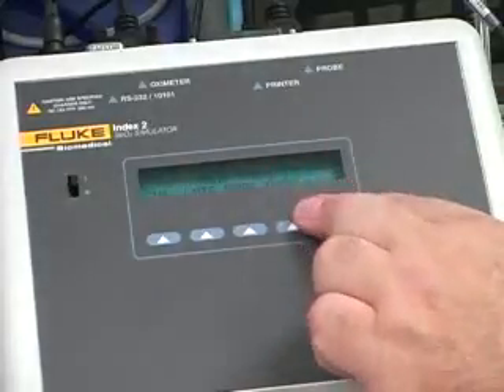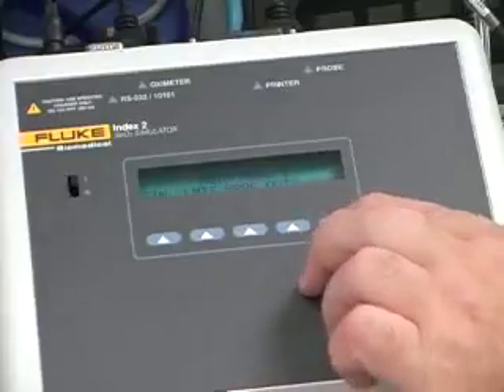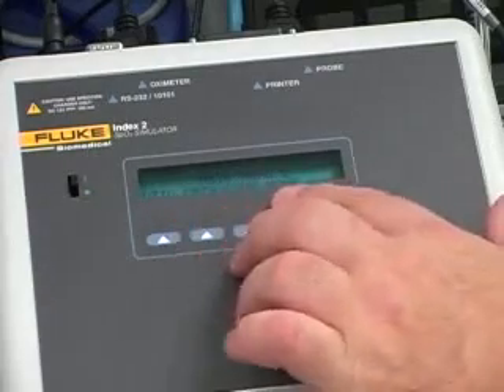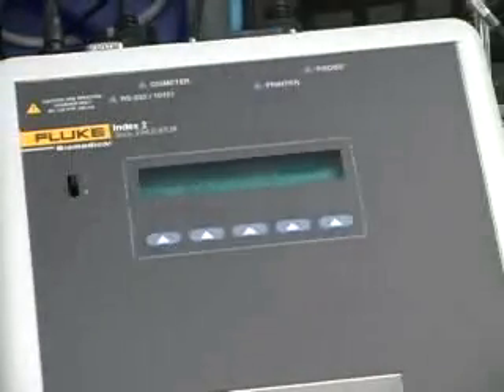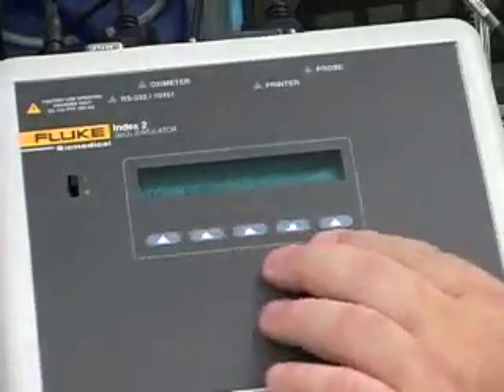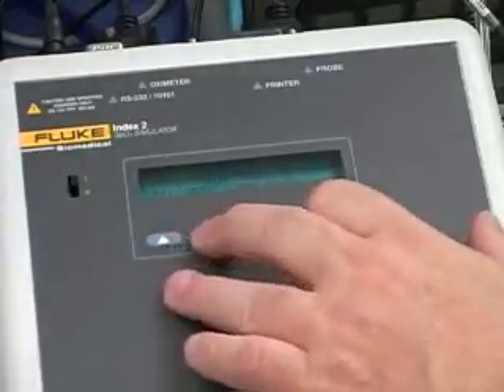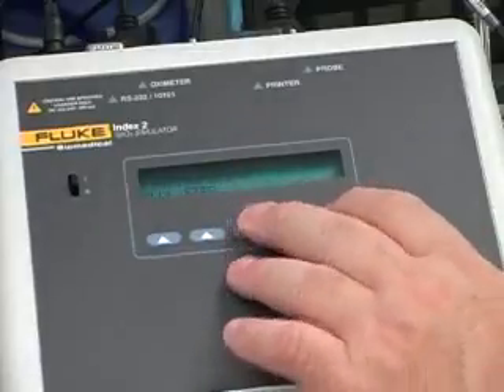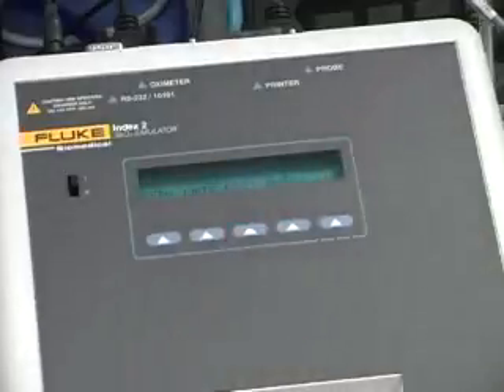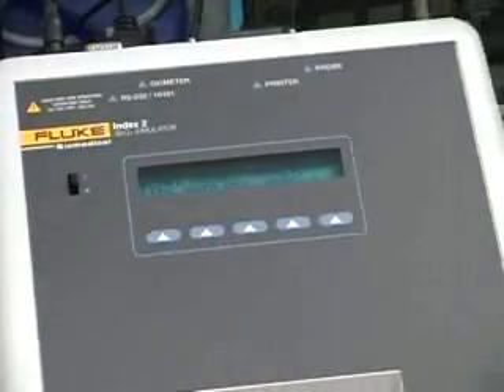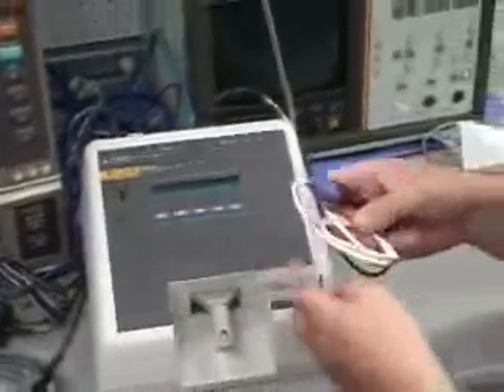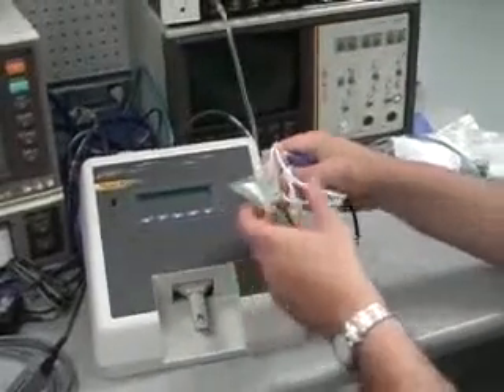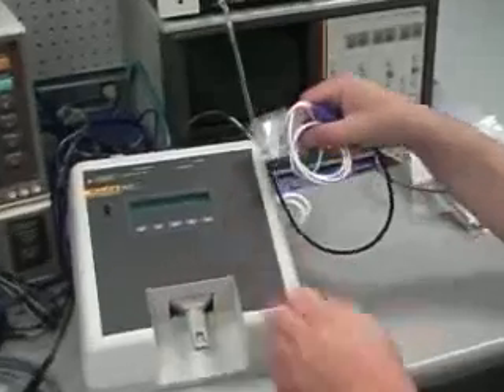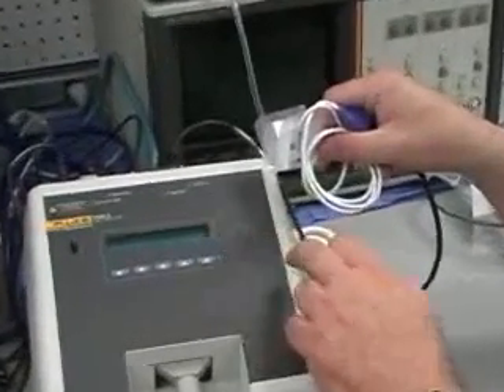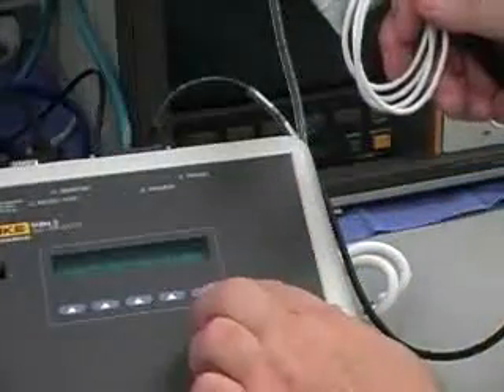Okey-dokey. Auto, we're going to cover more with a med tester. And just a couple of other options. These are more for programming, so I don't want to get into those at this point. And configuration. Also, you have the ability to do a basic probe test. This is with the electrical simulation version. Just pop in your probe, and you have the ability to measure resistance on the wire. That gives you the pinouts and the different resistances, so you can flex the cables and see how well they are working.